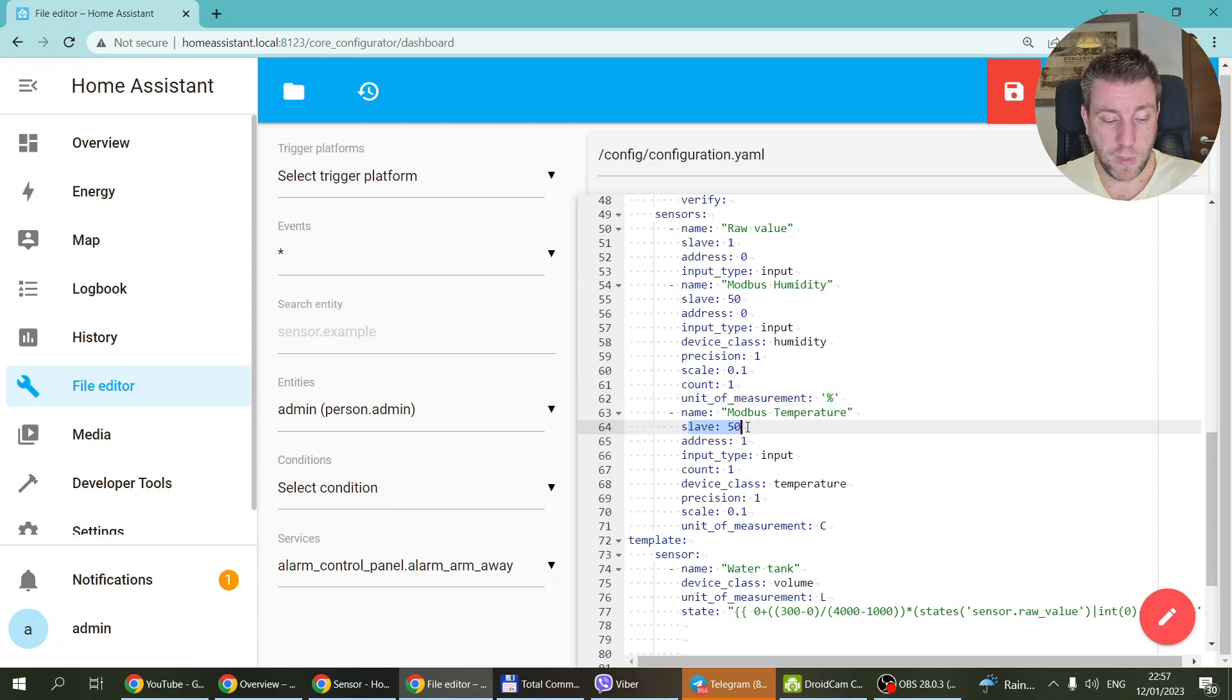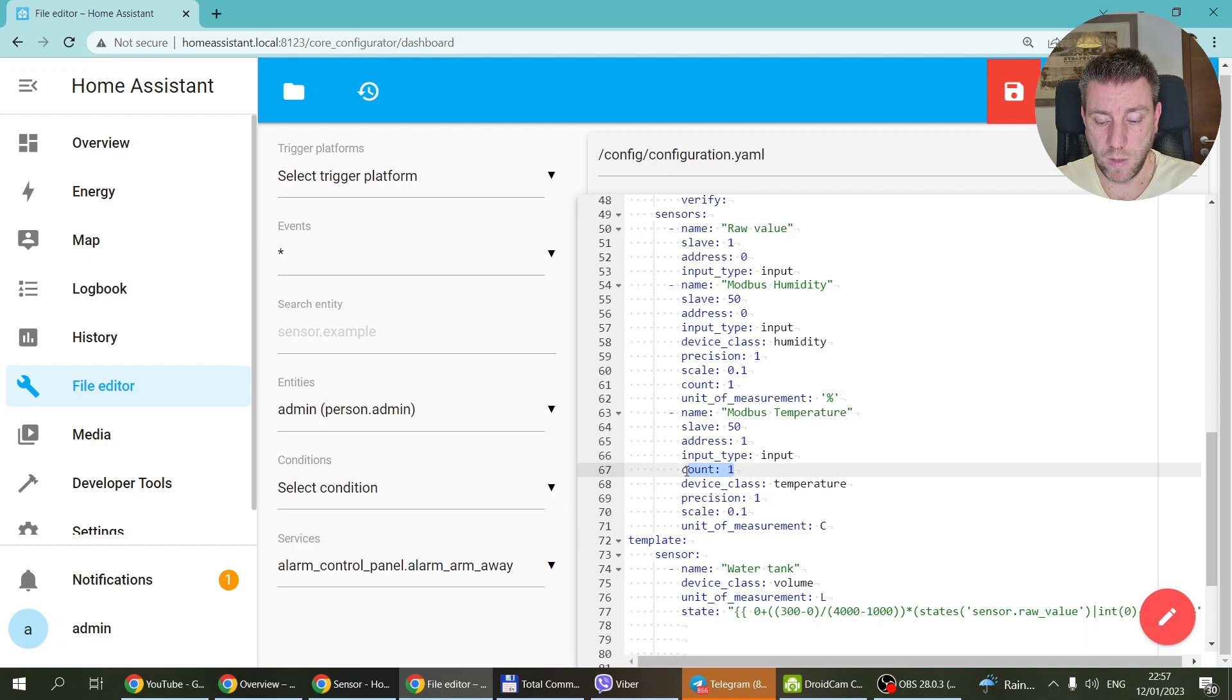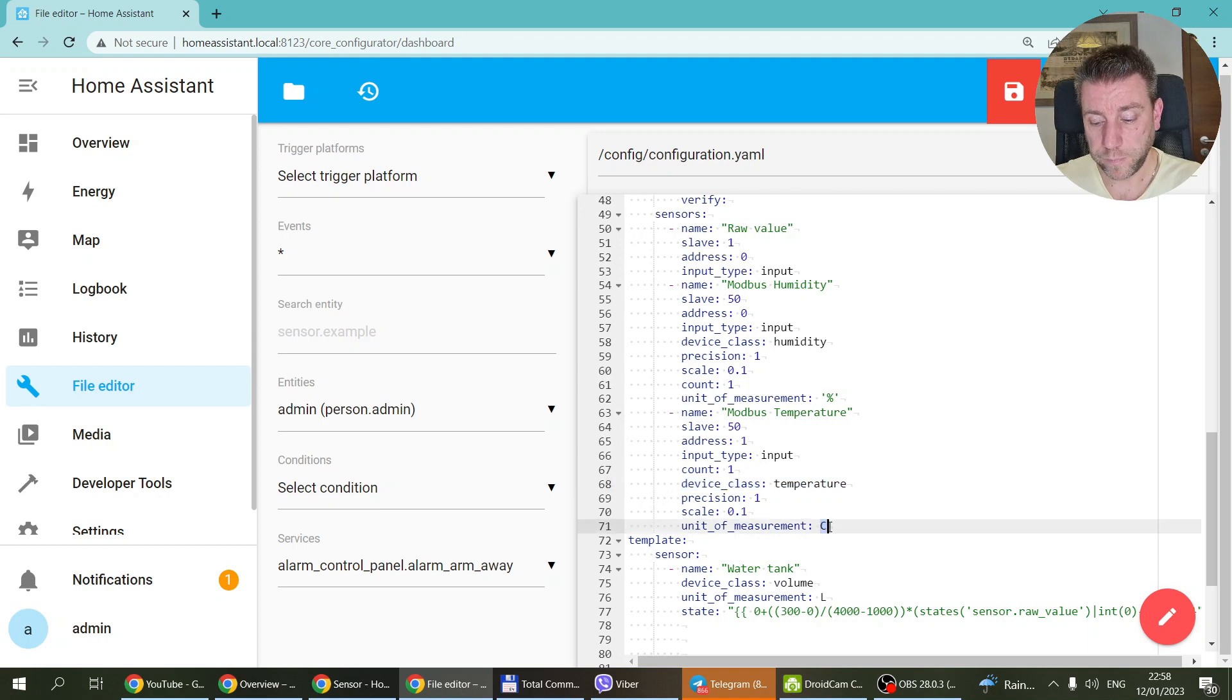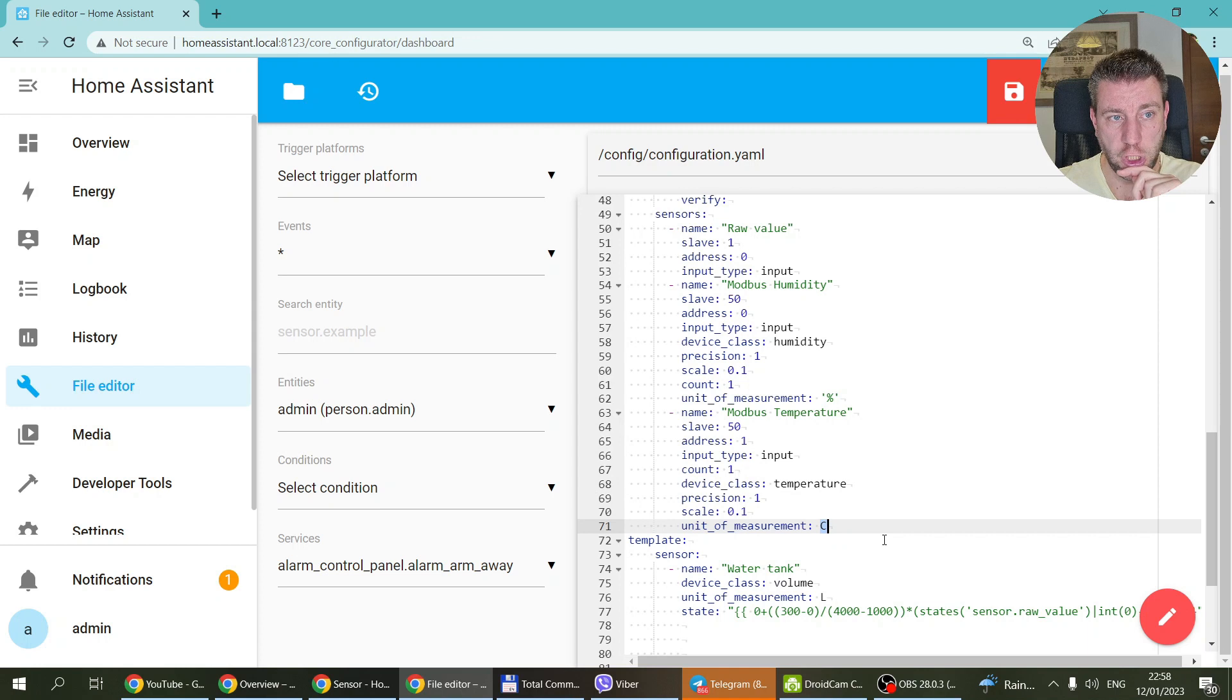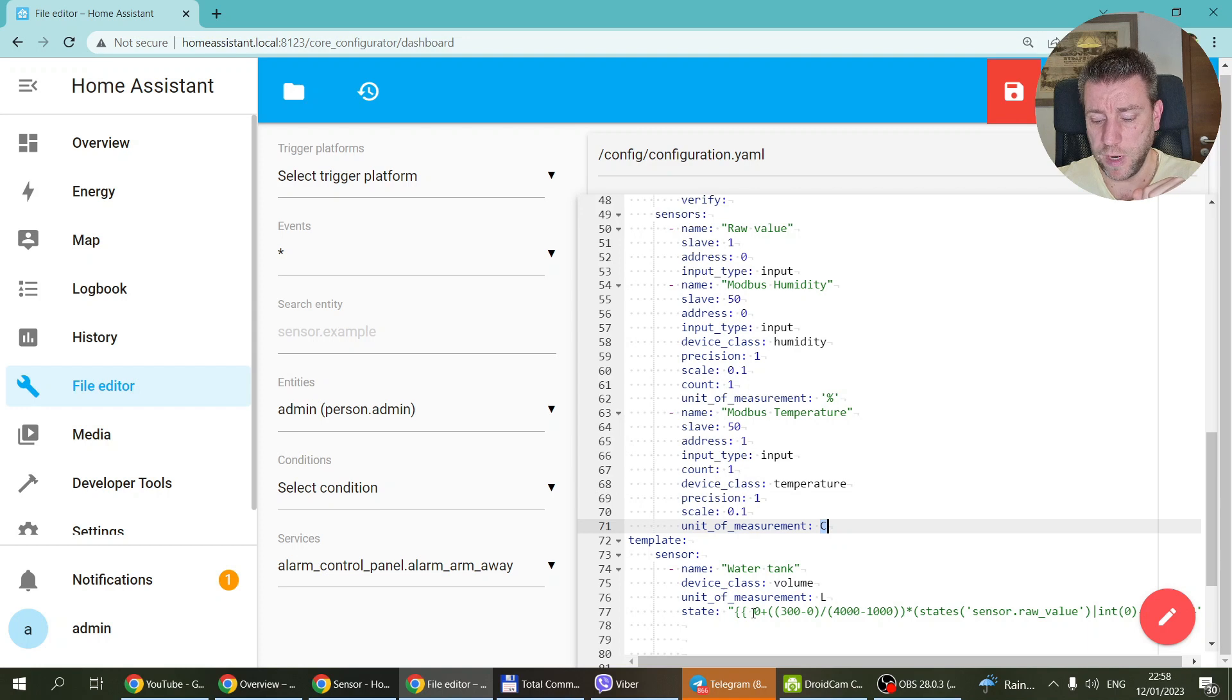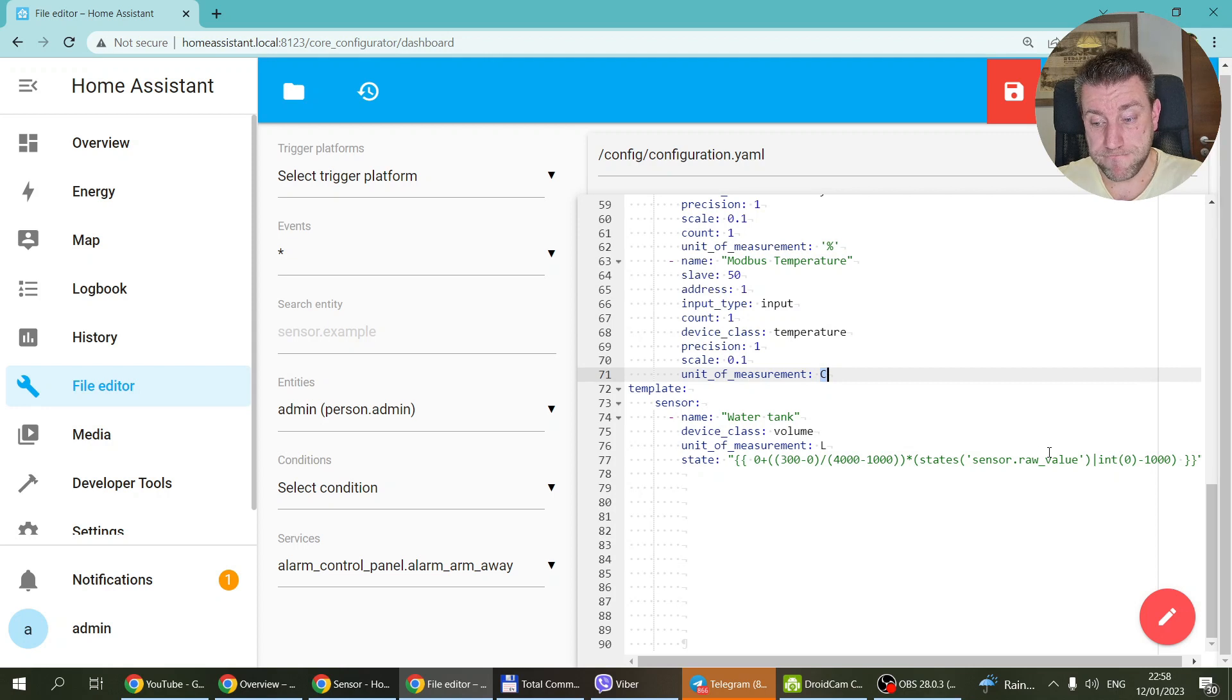And to configure the temperature, again, the slave is 50 because this has a Modbus address of 50. Now the address is one because this is the second input register. And the thing is the same. So the scale is 0.1. The precision is one. The count is one because we are just reading one register. I think I could have omitted this one. And for the temperature, the device class is temperature. And the unit is C because it's sending the values in Celsius. And that's a good question, how you would convert it to Fahrenheit. Because again, there is no Lambda function here. So I think for this, you probably have to create a sensor type again where you can use either the same calculation formula or maybe a Lambda function to convert the Celsius into Fahrenheit. But I think you can create a formula just like this to specify the conversion from Celsius to Fahrenheit.